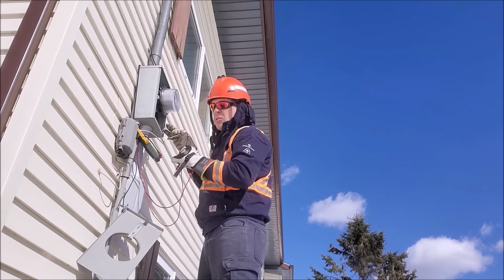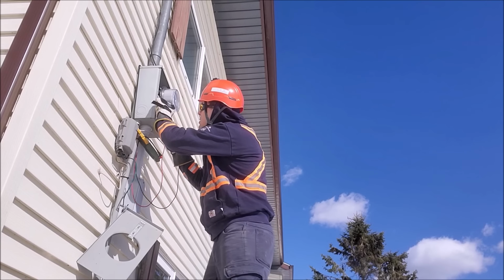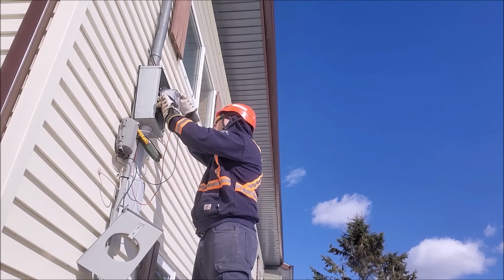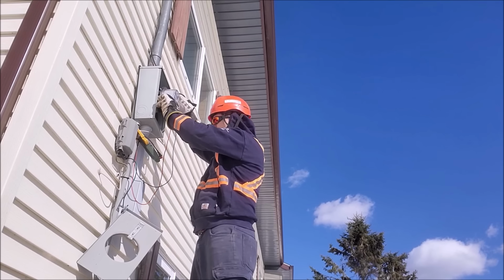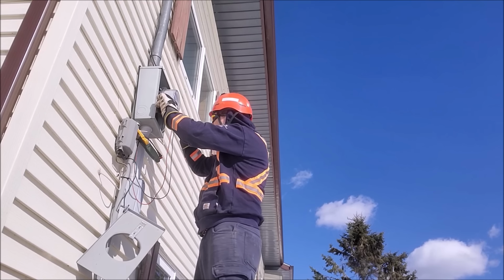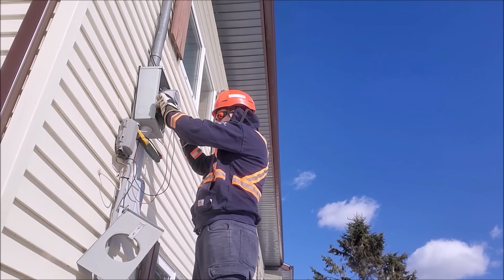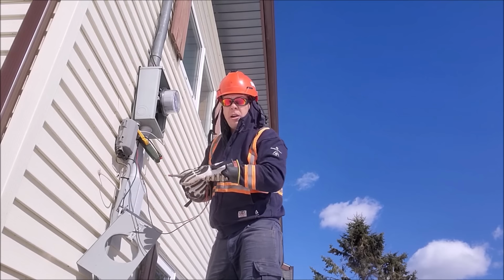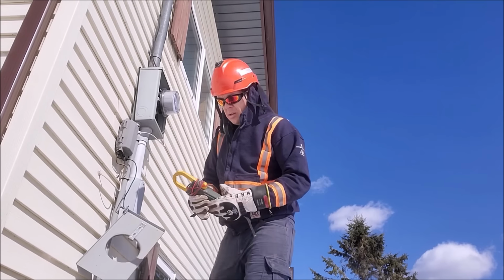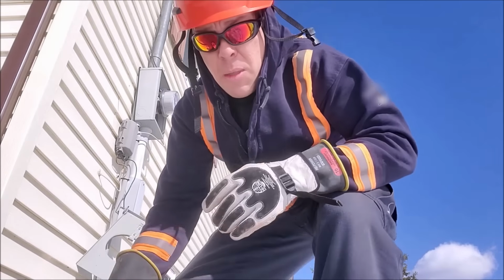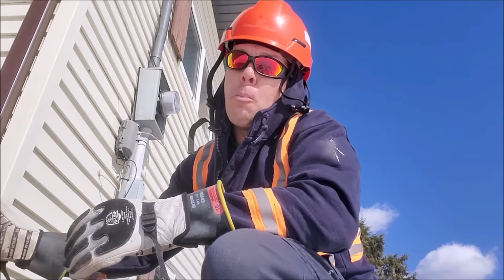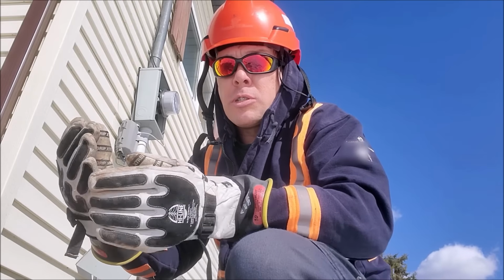Now first I want to make sure it's not the neutral in the actual box. So I'm going to check on the top side lug of the neutral, then the bottom side. Alright, we got the same thing in both cases. As soon as we get that neutral fixed up with load on, the voltage should go back to 123 volts per side.